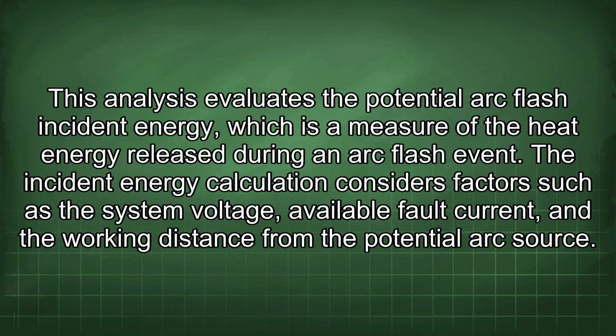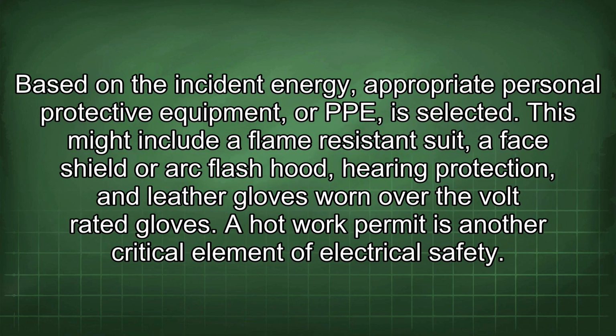This analysis evaluates the potential arc flash incident energy, which is a measure of the heat energy released during an arc flash event. The incident energy calculation considers factors such as the system voltage, available fault current, and the working distance from the potential arc source. Based on the incident energy, appropriate personal protective equipment, or PPE, is selected. This might include a flame-resistant suit, a face shield or arc flash hood, hearing protection, and leather gloves worn over the volt-rated gloves.